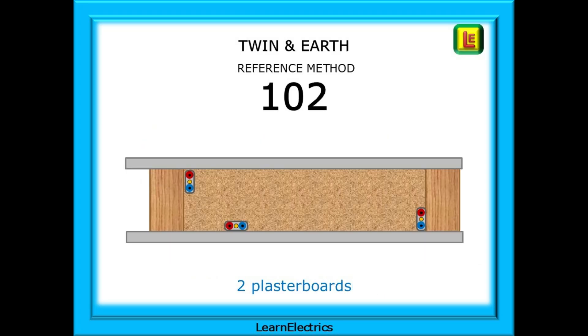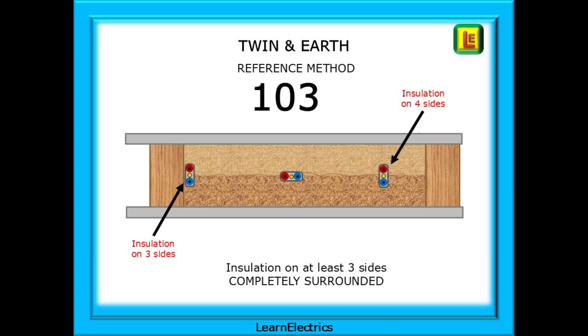Reference method 102 has the cables in the same positions as the previous slides, touching the joists or plasterboard, but now there are two plasterboard surfaces. The cables might be encased in a stud wall. So 102 - two plasterboard surfaces. And now reference method 103 - look at the position of the cables. The cable clipped to the joist now has three of its sides surrounded by thermal insulation. The other cables shown here are completely surrounded by insulation - the worst case scenario for heat loss from the cable. So 103 means at least three sides are covered by insulation.